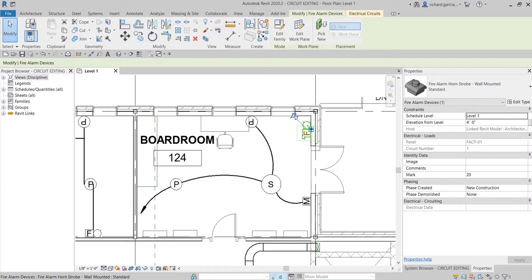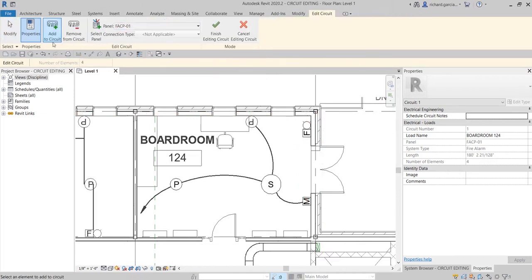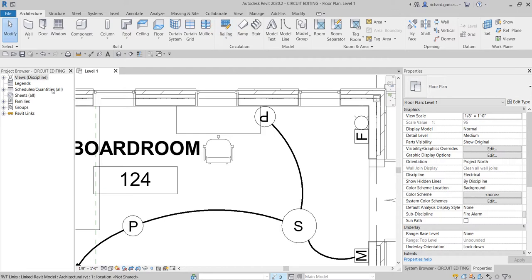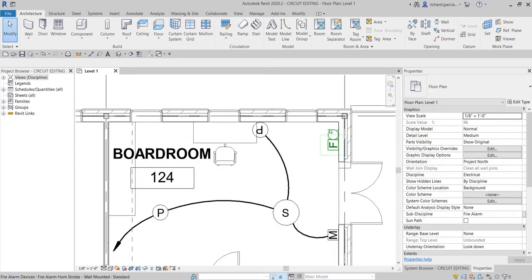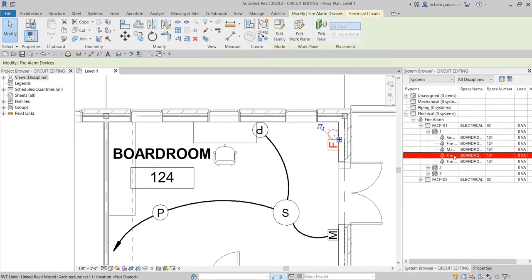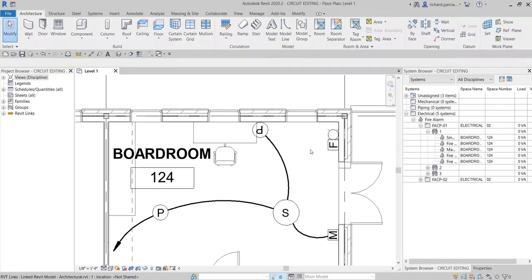Now I'll select the device that is already part of the system — it's assigned to circuit number one on FACP 01. Going to the Electrical Circuits contextual tab and selecting Edit Circuit, with 'Add to Circuit' selected, I'll click the speaker device to add it. The total becomes five. After selecting Finish, checking the system browser confirms it is now listed under FACP 01, Circuit 1.